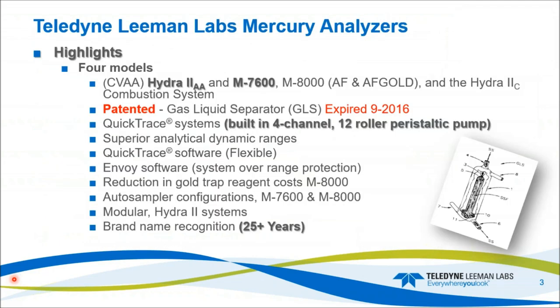Some of the highlights for the Teledyne Leeman Labs mercury analyzers. We have four models: the CVAA systems, the Hydra IIAA, the M7600, the M8000 which is atomic fluorescence and atomic fluorescence with gold, and then the Hydra IIC combustion system. We have a patented gas liquid separator for the QuickTrace systems — the patent expired in 2016. The QuickTrace systems have a four-channel 12-roller pump. All systems have superior dynamic range. The software on the QuickTrace is extremely flexible, and the Envoy and QuickTrace have over-range protection. We have gold trap reagent saving costs in the M8000 CVAF system, auto sampler configurations for the two QuickTrace models, and 25-plus years of brand recognition.